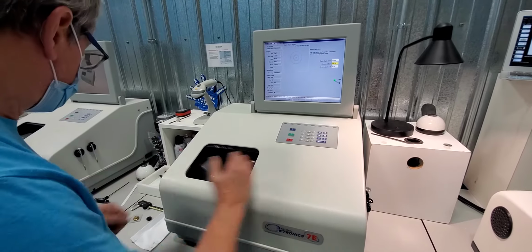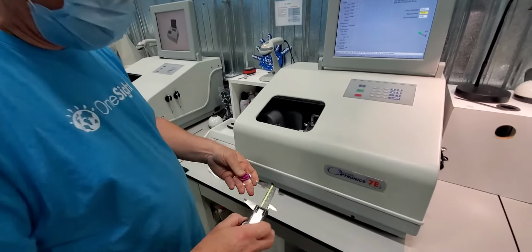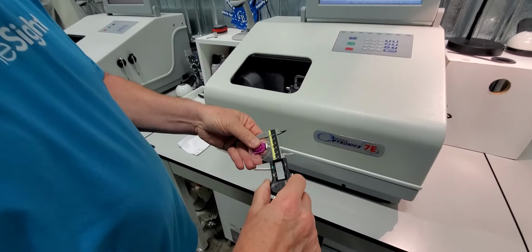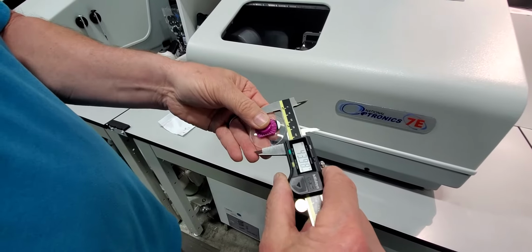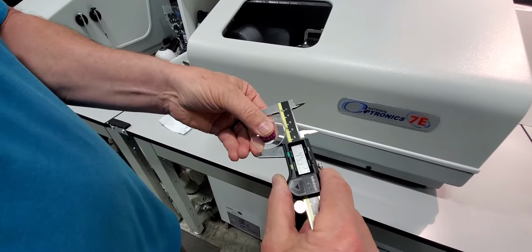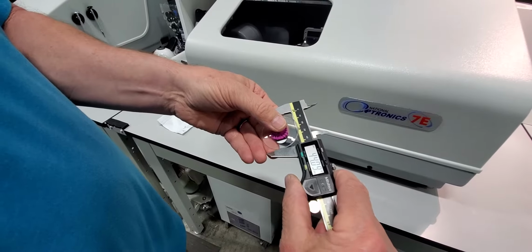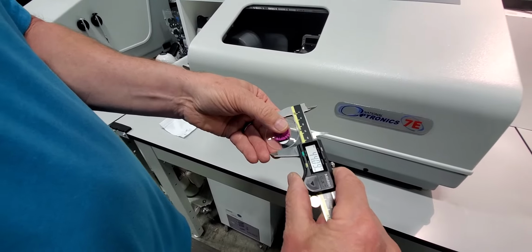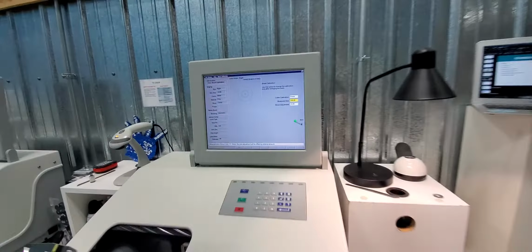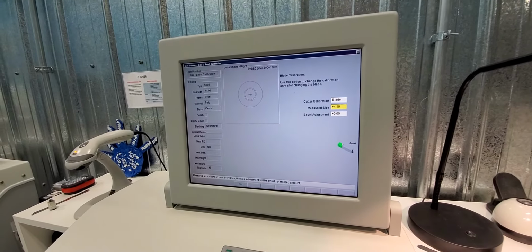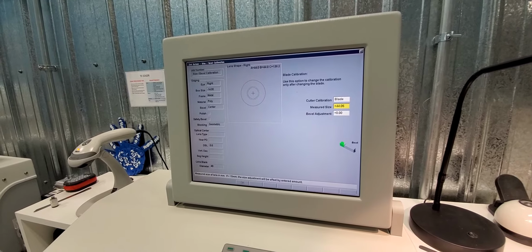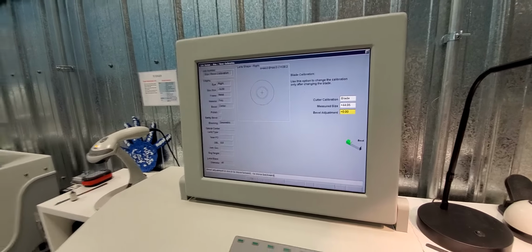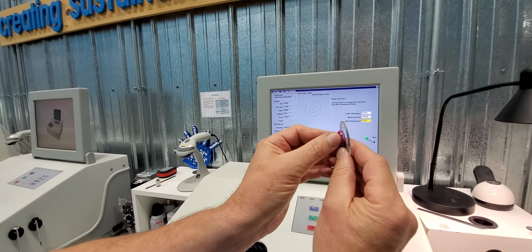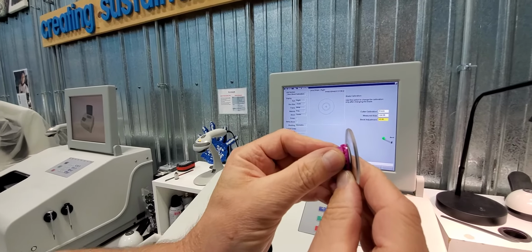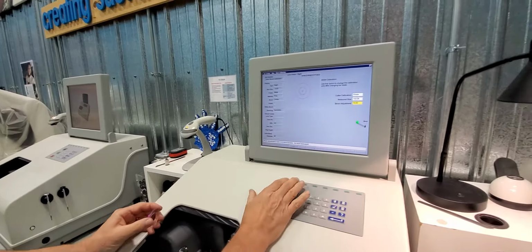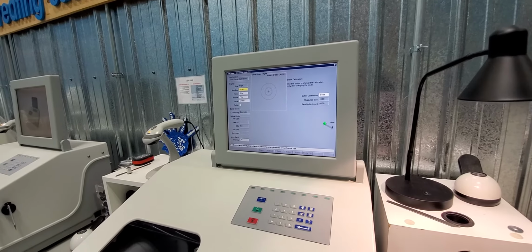So you want to remove your calibration disc, take your calipers, check it in. You're going to check it in 2 directions. And then you're going to put in the average of those two. You're going to enter into the machine. You also want to check your bevel placement. Should be in the center. Right in the center of the lens. That looks good. Hit OK, and you're all set.